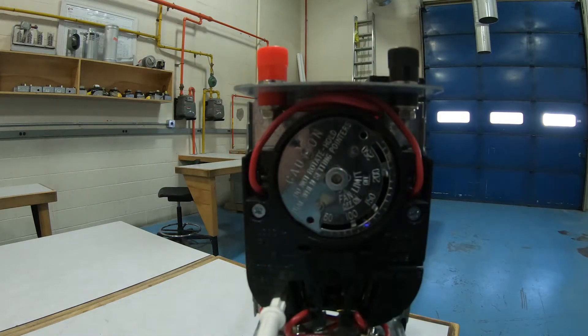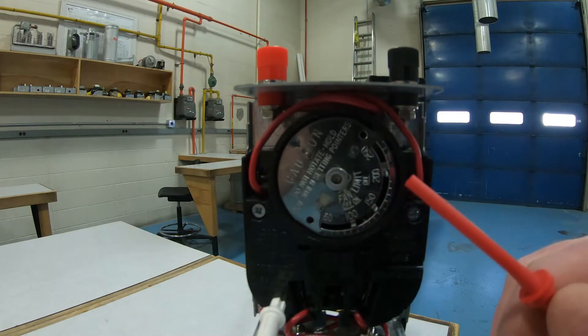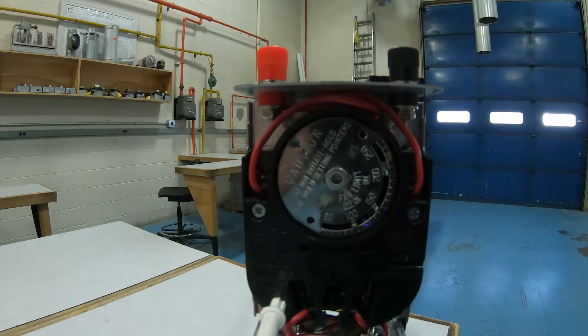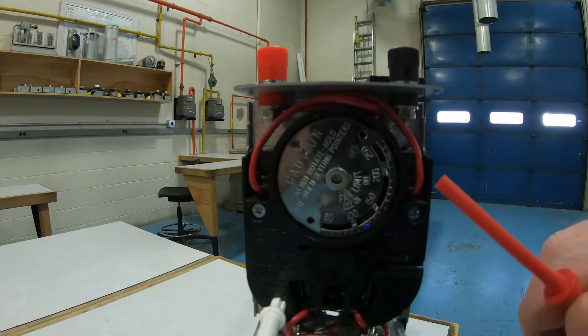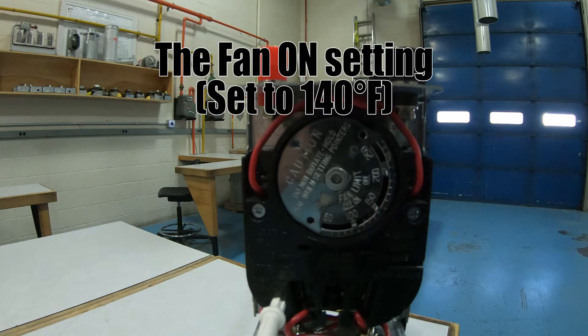So we have three typical settings on a combination fan limit. The fan off is the first little tab here, the fan on is the second tab, and the high limit setting. Now let's talk about this in order of operation. What's going to happen? Furnace is off and all of a sudden the thermostat says hey, the house is getting cold, furnace turn on. So main burner starts up. Nothing's happening right now except for the heat exchanger is heating up, and eventually it'll get up to, in this case, 140 degrees Fahrenheit, and all of a sudden the fan will click on.